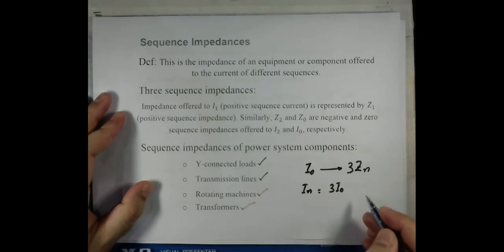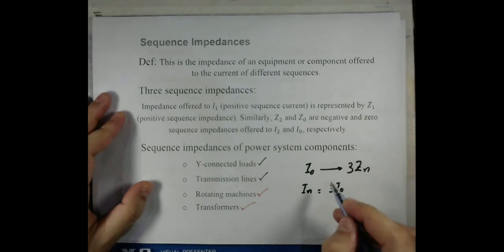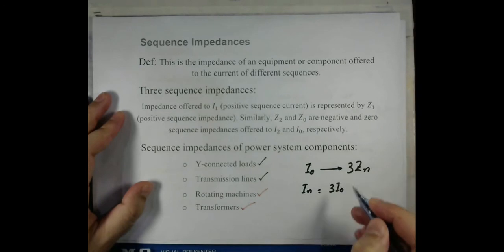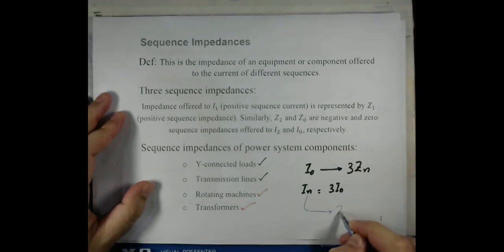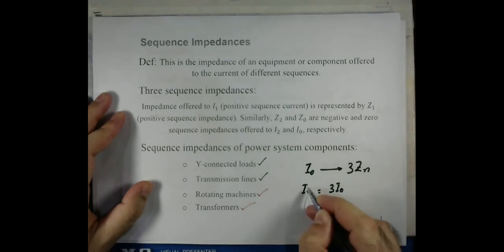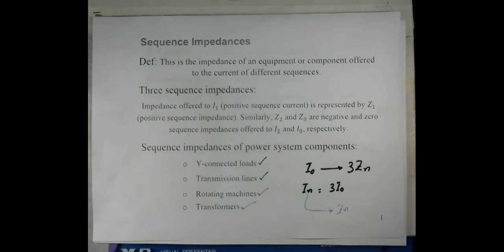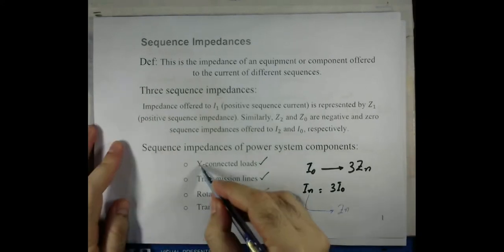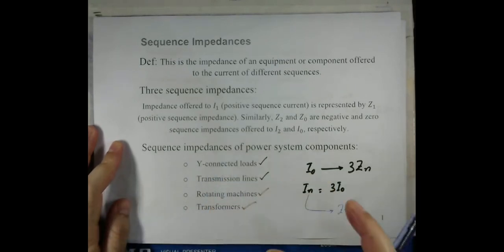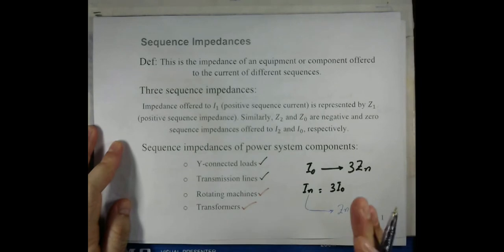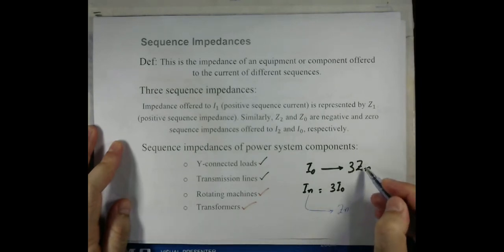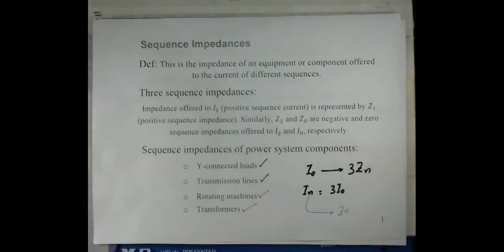The actual impedance is ZN and the neutral current is 3I0, so the impedance offered to the neutral current is ZN. If we multiply this current with ZN, we get the voltage drop across ZN. The important observation was that if the neutral point of the Y-connection is not grounded, the zero sequence network will be an open circuit, and both positive and negative sequence currents do not flow through the impedance to the ground.